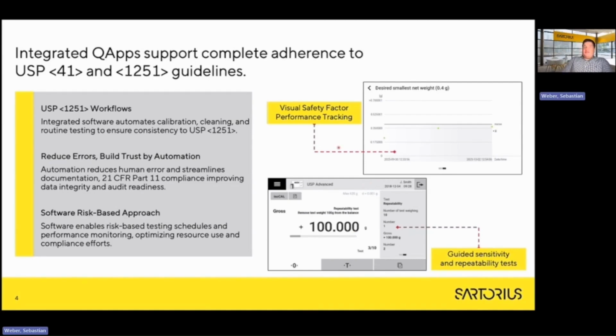You see as a dot all the test results from the past test runs. You can directly see if they are green, they are within the specification. If they become red, they are outside the limits. You also see the limit line here, and then you can directly assess: are all my test results within the specification? Are they out of specification, or only some of them? And are they very close to the limit, or far beyond the limit? And this also allows you to support your risk-based approach in the end.